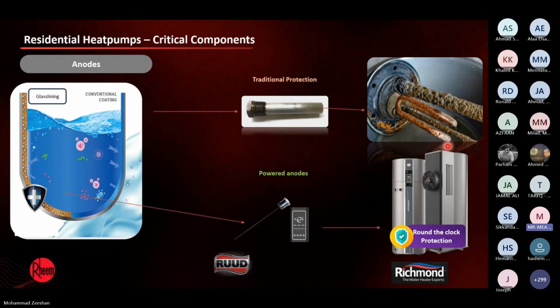So we have glass lining on the tanks. This is there to protect the steel itself. However, these are not completely clear coated. They have pores in them where the water can come in contact with the steel. You can't have a glass lining that completely covers the tanks because it becomes brittle. So during transportation, there are chances that it will break, and in any case, it will start corrosion.